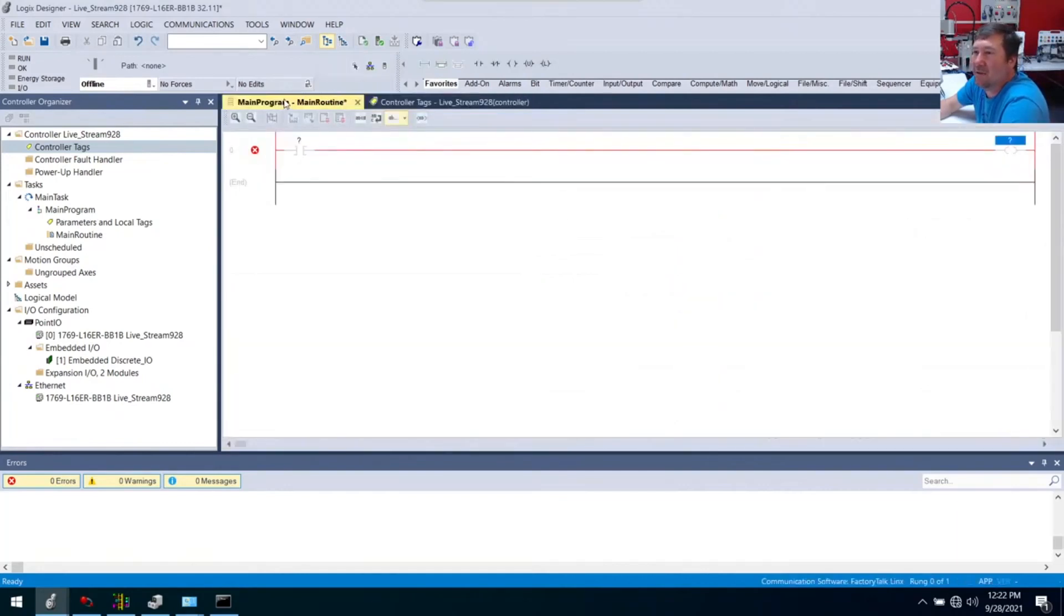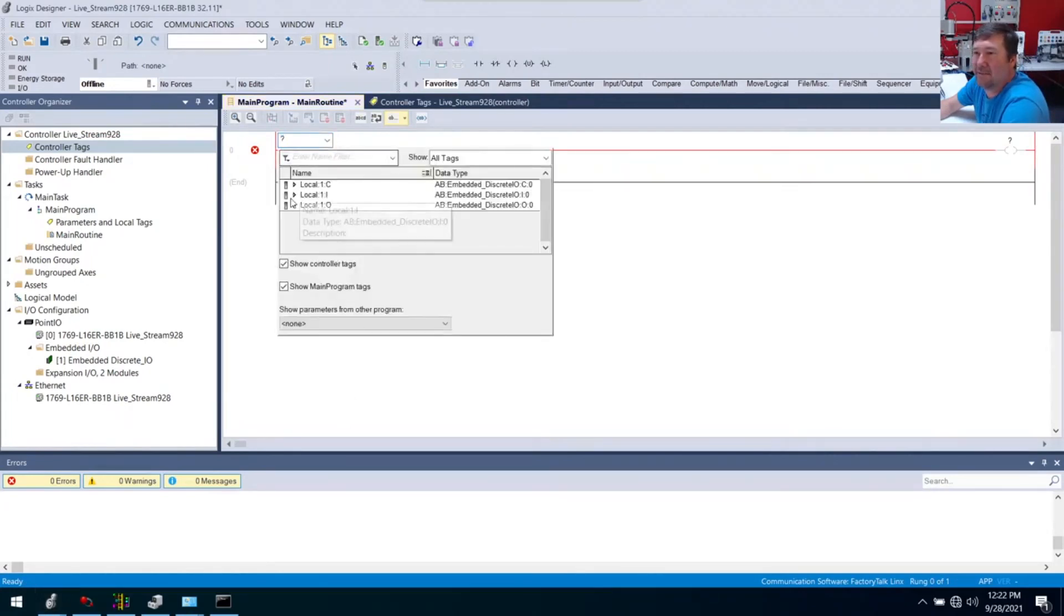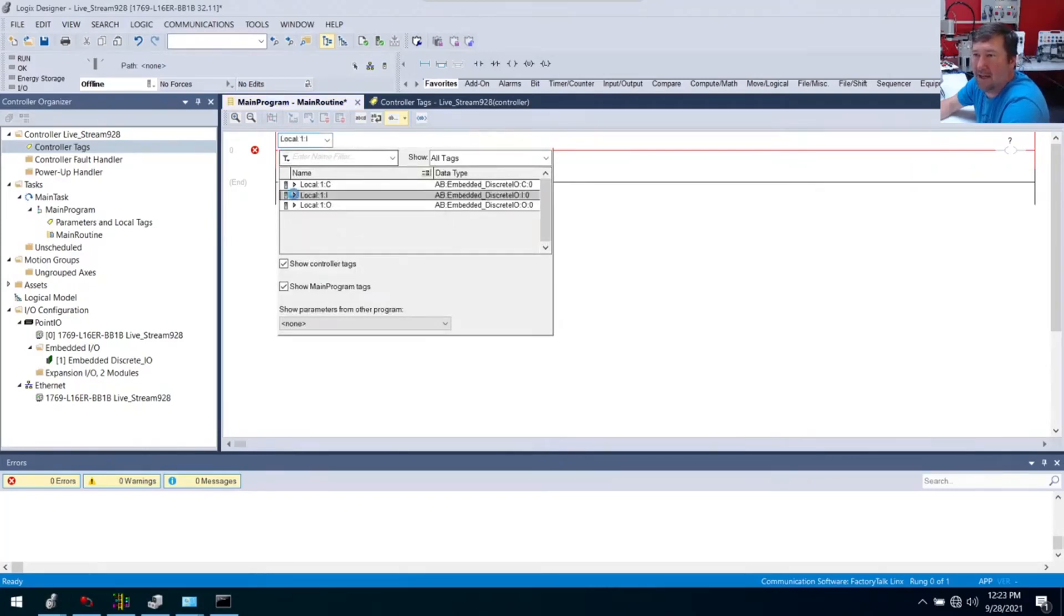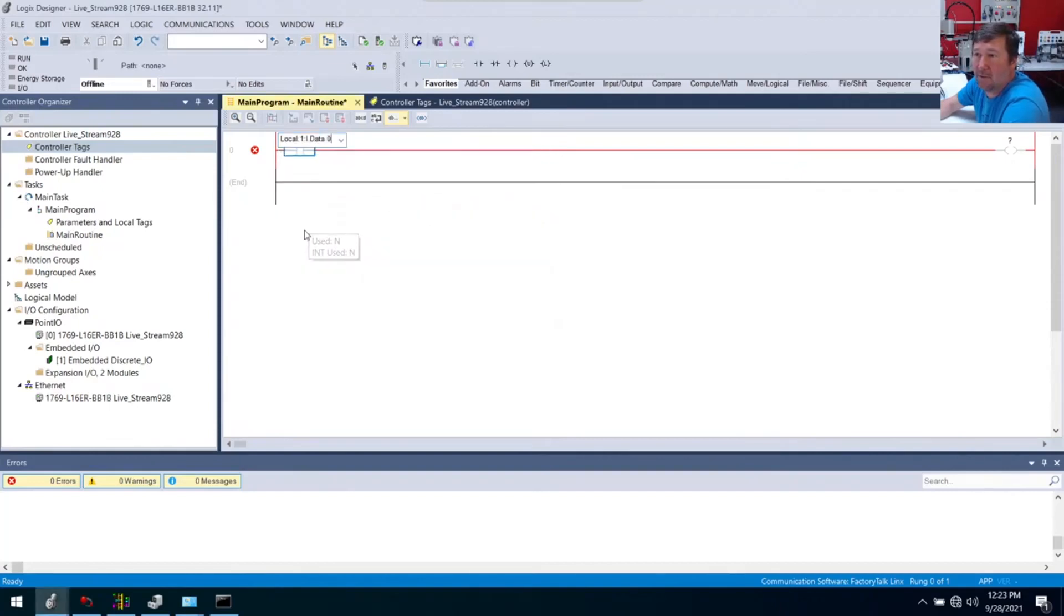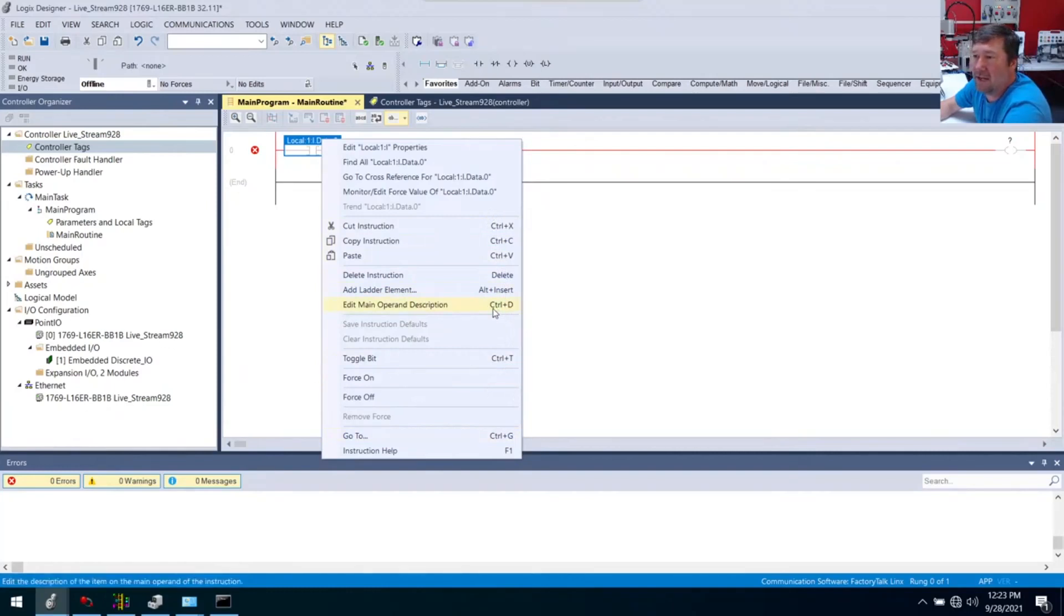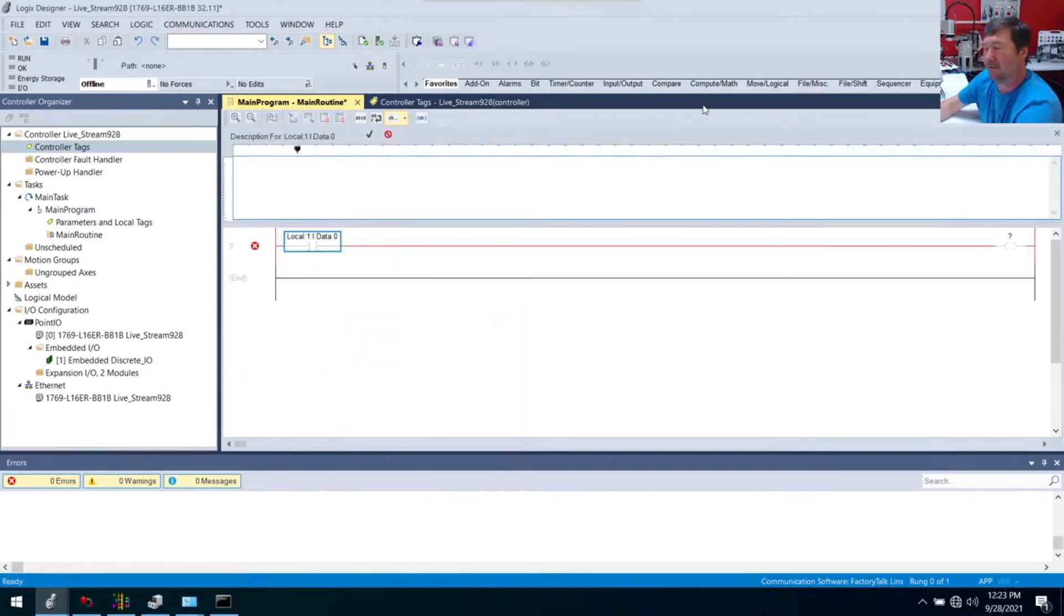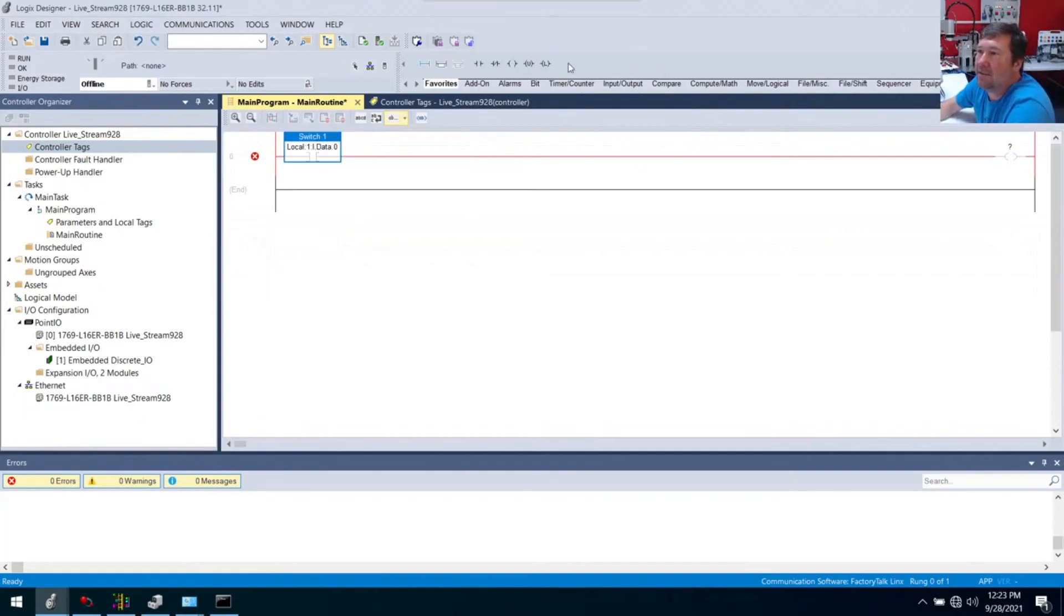Over here we want this to be input number one, same as over there. If you'll double click here, you actually get a dropdown. We can click it and navigate through here. We have local, and then we know it's 1:I. I'm going to open that up, and then we're going to have data. There's point number zero, this is going to be input zero. Again, we're going to put a description on that. I love about Studio 5000, you right click and get lots of options. If you're not sure how to do something, right click and see what options come up. We're going to edit the main operand description. Every time there is a shortcut code, they put it right here. From now on I can just hit Control D and do a description. This is going to be switch one.